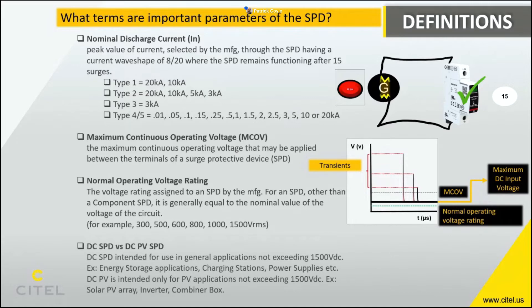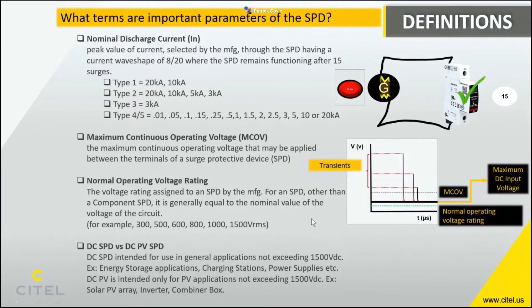It's important to make sure you have the right certification, as failure tests differ between DC SPD and DC PV SPD. DC SPD certification is required for applications like EV charging stations, energy storage systems, DC rail, or DC power supplies. If you have a solar array, inverter, or string combiner box, you need a DC PV SPD certification from UL.